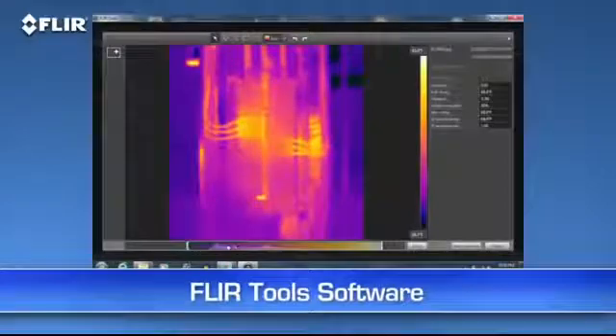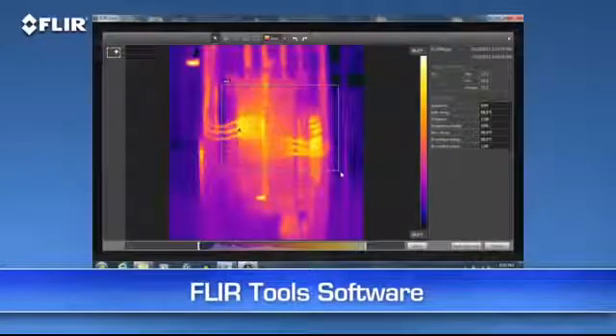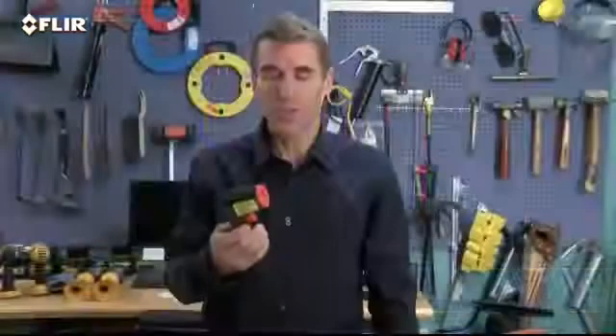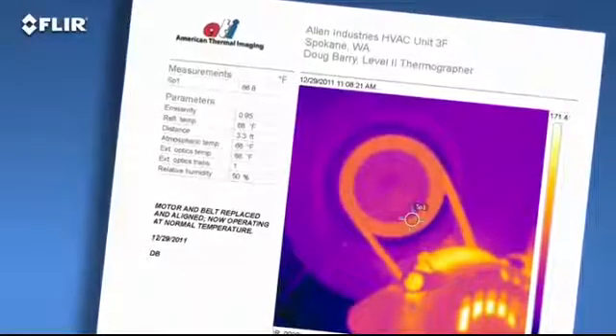Adjust the levels, change the palette, add more measurement tools. Capturing images that have all this stored temperature data and analyzing it later makes it easier to measure any spot on the image — certainly beats jotting down dozens of readings from one of these. Even better, FLIR Tools can help you create a professional report in no time to reinforce your findings so you get an answer back faster and you can get repairs underway.